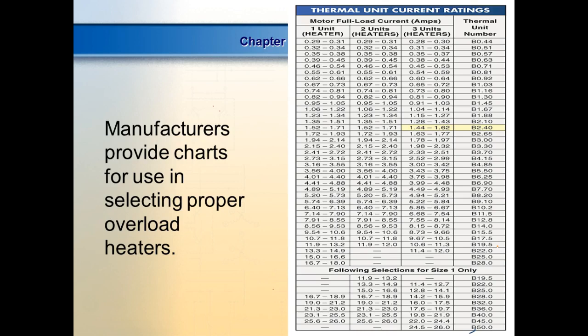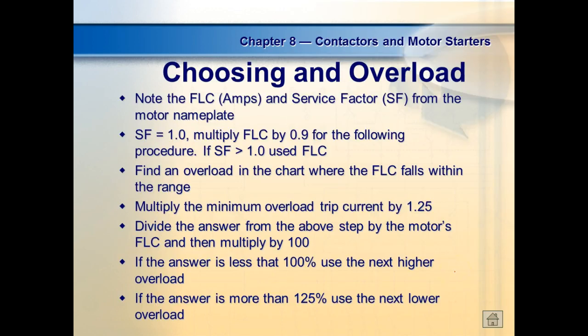Usually not constantly, but safely without doing what? Without burning it up, right? Or stalling. So this is what we'll do. We'll look up the amps on the full load current, or the amps on the nameplate. We'll make sure we find the service factor and also the number of phases. I think all the ones that we have are single phase. I couldn't find a nameplate on a single phase motor that was not internally thermally protected. So we'll look for the full load current within the chart that falls within that range.